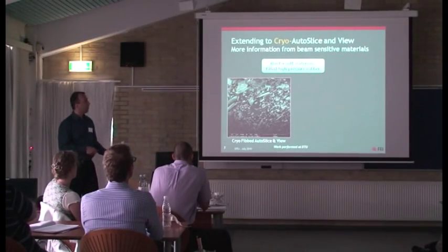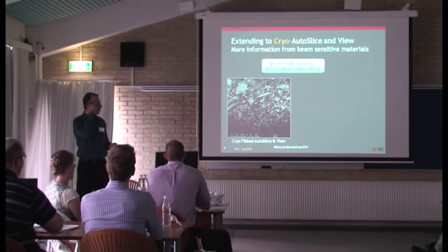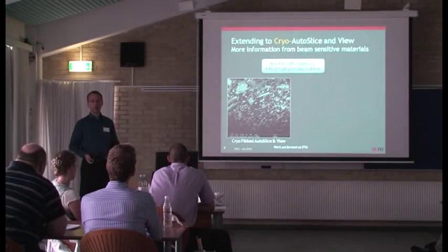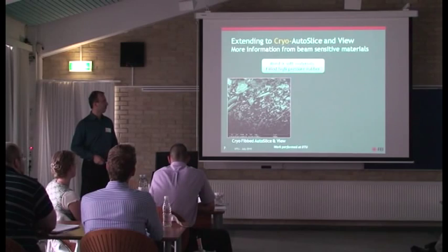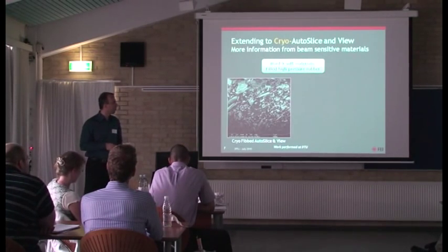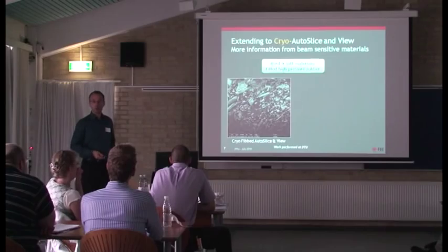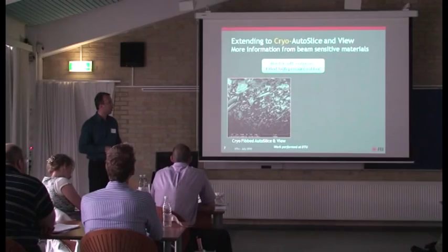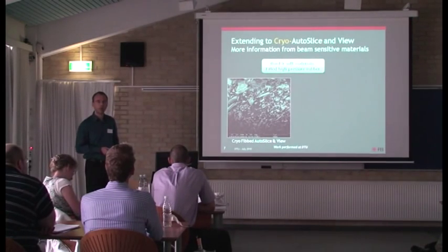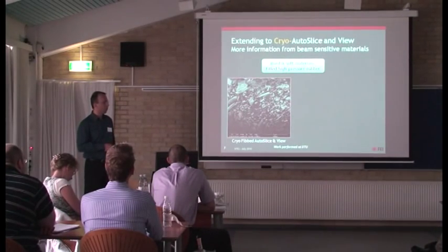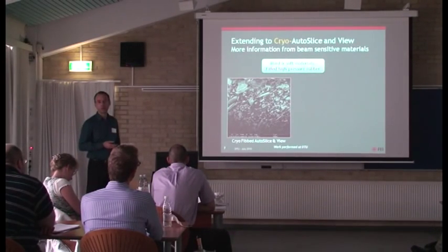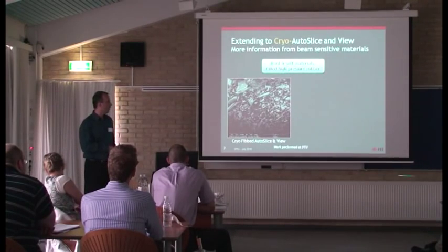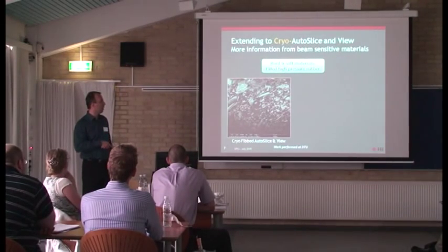And then, moving on from the traditional SEM images, there are now definitely possibilities to deal with other types of problems that we encounter, more and more going to a wider range of materials. Starting with those materials which are sensitive to the electron or the ion beam, it becomes possible to cool the sample to typically minus 150 degrees and get contrasted SEM images from those samples.